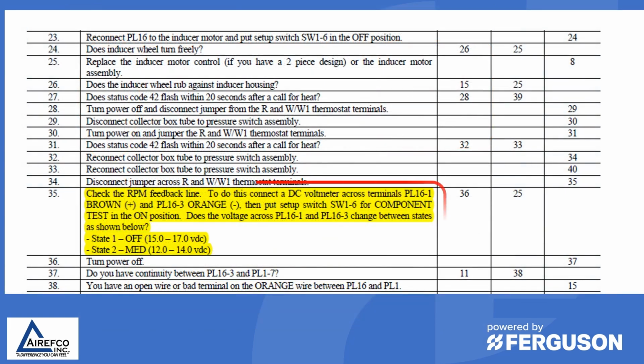So in this step 35, we are being told to check the RPM feedback line. Some ECM motors have this feedback line where the motor is telling the board what it is actually doing. So between the brown and orange wire on this motor, when the motor is off, you should read 15 to 17 volts DC. And when it's commanded to run, you should read 12 to 14 volts DC.